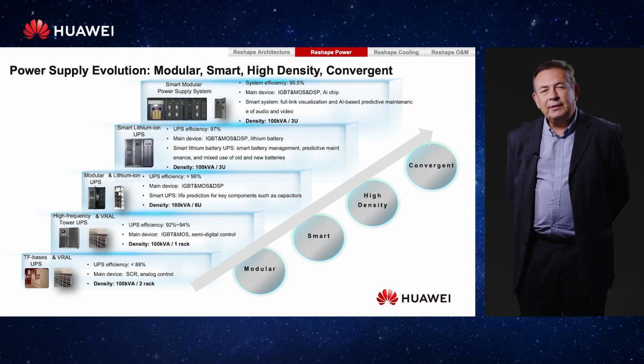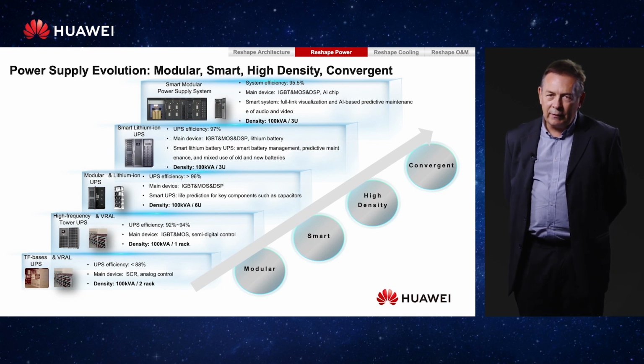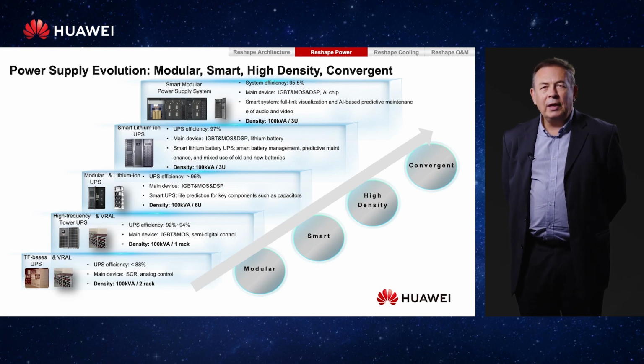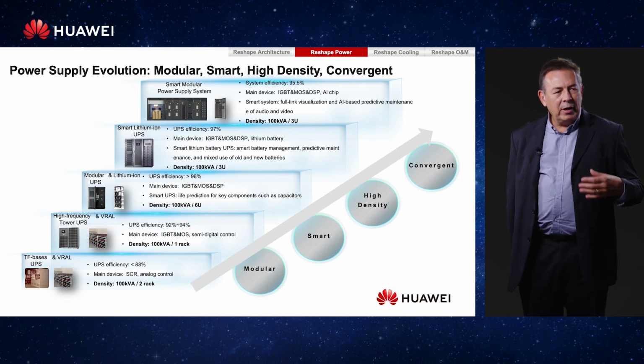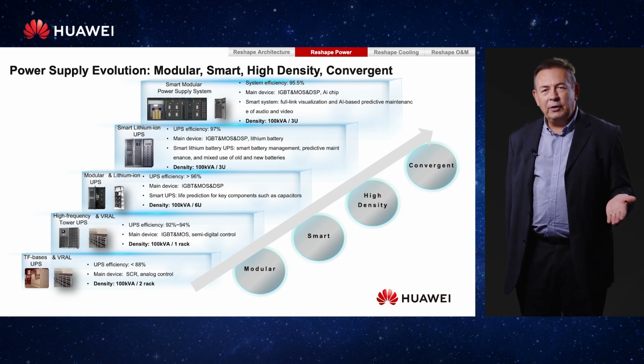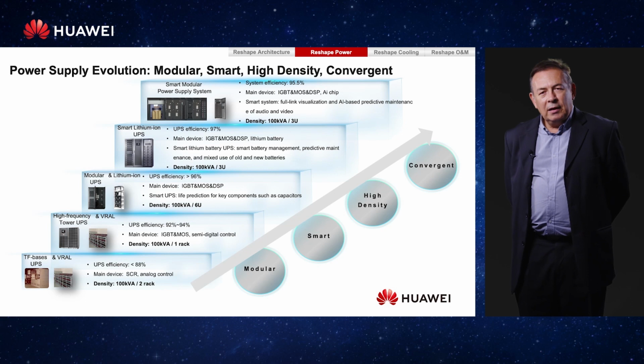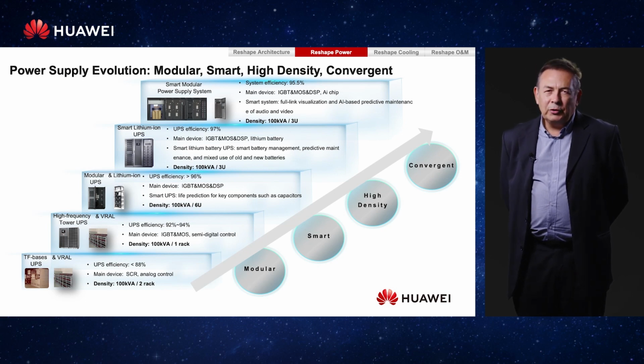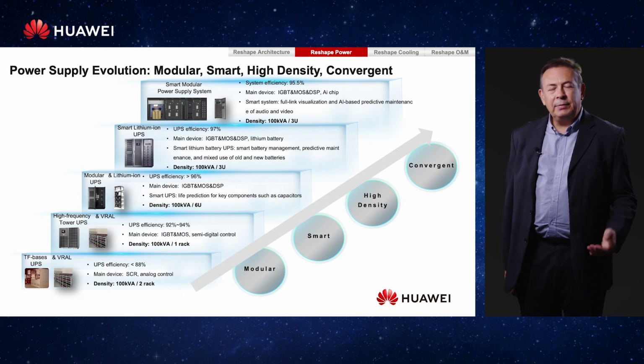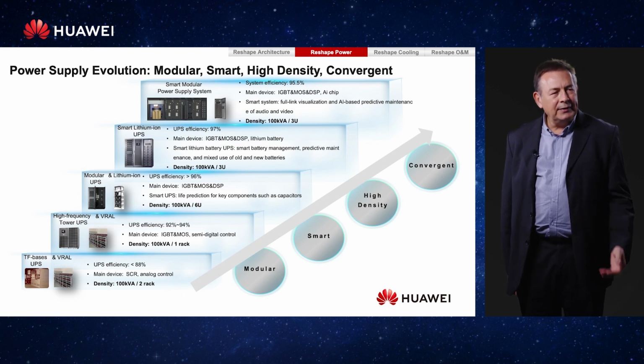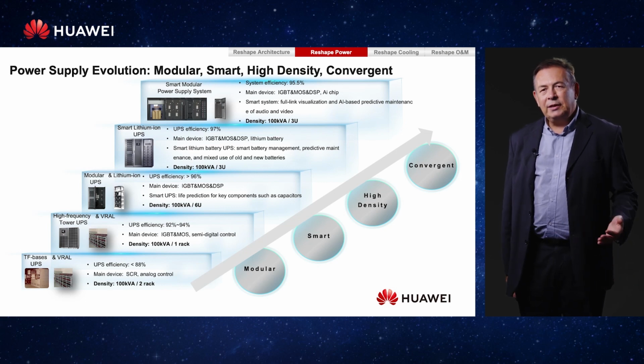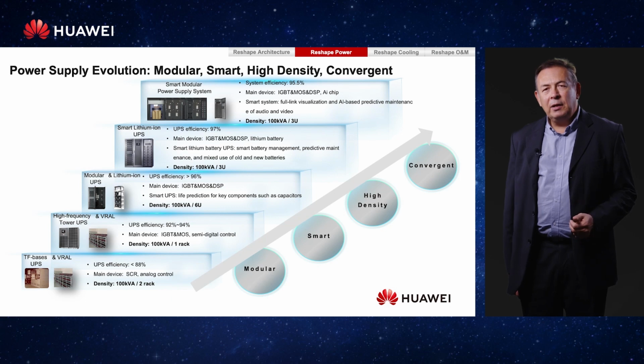Then we moved to modular UPS, and Huawei has been keen on developing and improving this technology over the years, together with lithium-ion. Efficiency moved up to 96%. At the time we got 100 kVA in 6U, the first generation. A bit more than a year ago we introduced a new 100 kilowatts in 3U modular UPS. Now we're talking about 97% efficiency, very high power density, and associating this UPS with SmartLi, our latest generation of lithium-ion batteries.